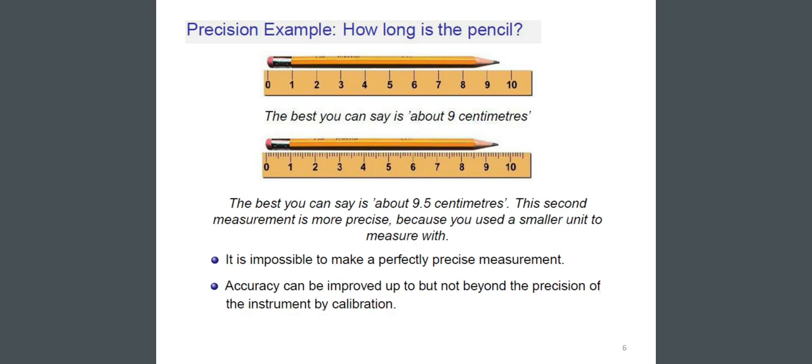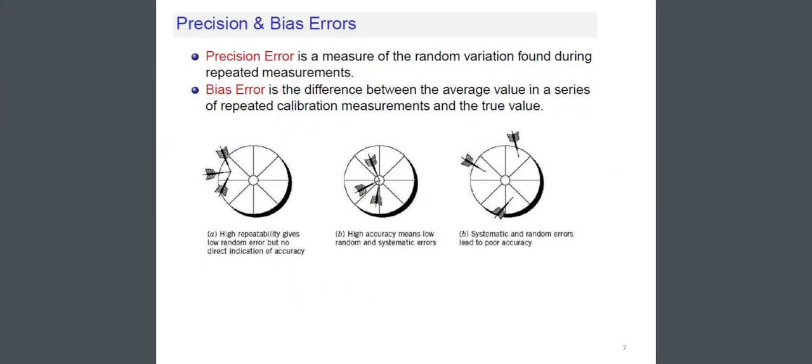Accuracy can be improved up to, but not beyond, the precision of the instrument by calibration. Precision and Bias Errors: Precision error is the measure of the random variation found during repeated measurements. Bias error is the difference between the average value in a series of repeated calibration measurements and the true value.